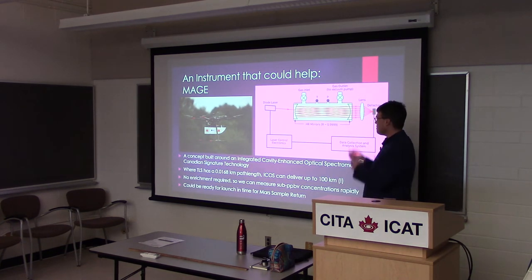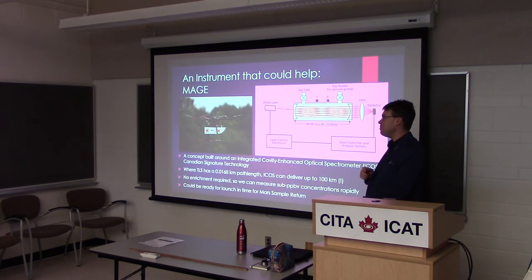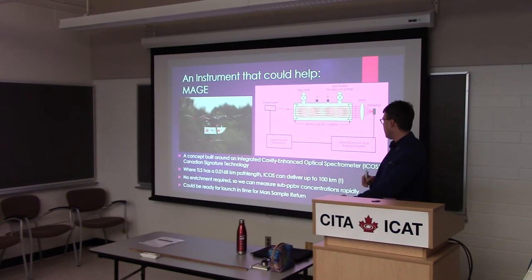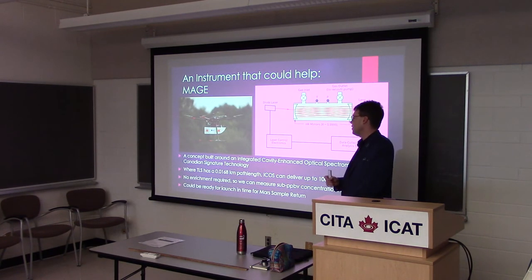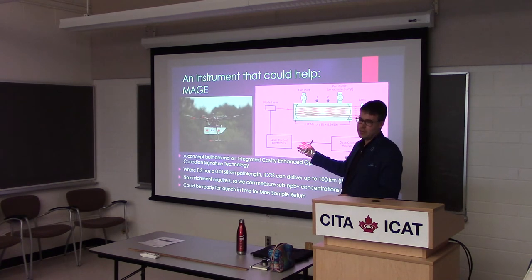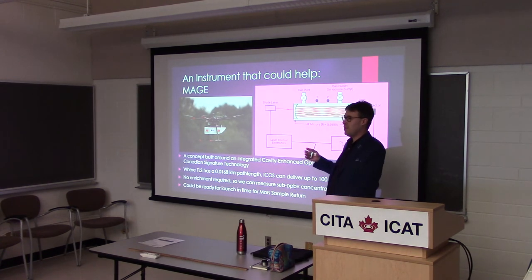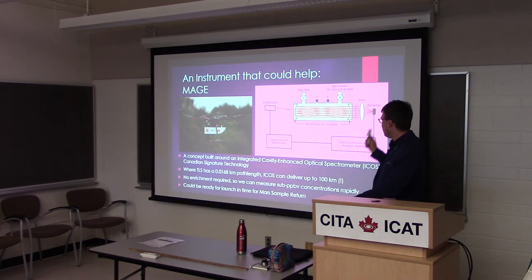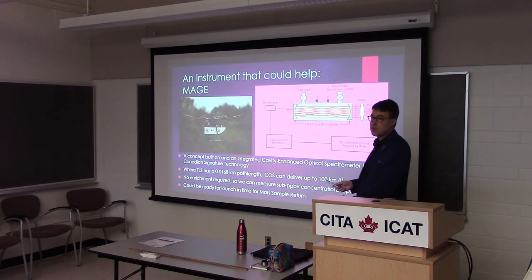So, what is MAGE? This is something I've been working on with ABB out in Quebec. It turns out that optical spectroscopy for gas analysis has come an awful long way since we launched the TLS and first conceived that way back in the early 2000s. Here's an integrated cavity-enhanced optical spectrometer. These things are robust. They put them on cars. They fly them on drones. One even spent several weeks on top of a streetcar in Salt Lake City getting bounced around. What's great about this thing is you get a phenomenal amount of path length from these very highly silvered mirrors.